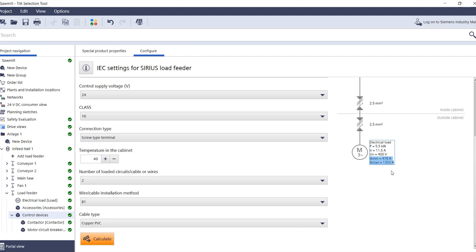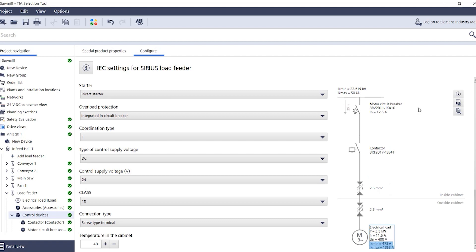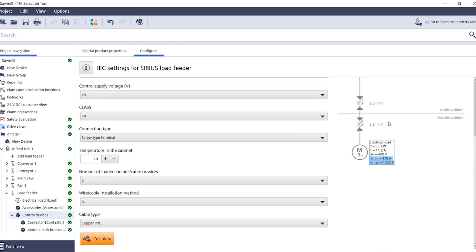One important detail remains to be said. The load feeder configurator plus configures the cable in such a manner that the minimum short circuit current is always high enough for the protection device to clearly detect a dangerous single pole fault.